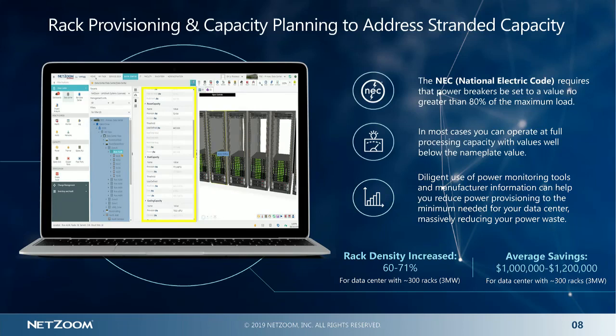We know that with data centers today, there are a lot of empty RUs in a lot of racks, and it doesn't have to be that way. But many people feel forced to configure their racks like this, leaving stranded capacity in both space and power. Why? Because most racks are provisioned based on device nameplate values, the maximum power draws set by the manufacturer.